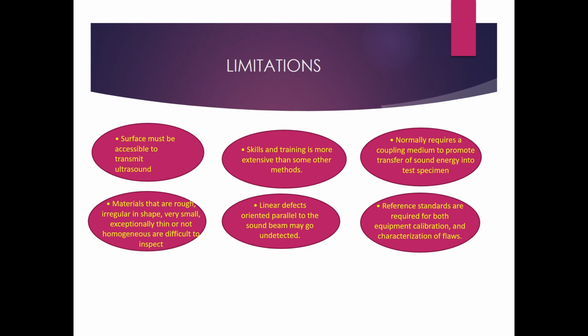Linear defects oriented parallel to the sound beam may go undetected. The last one is that reference standards are required for both equipment calibration and characterization of flaws.